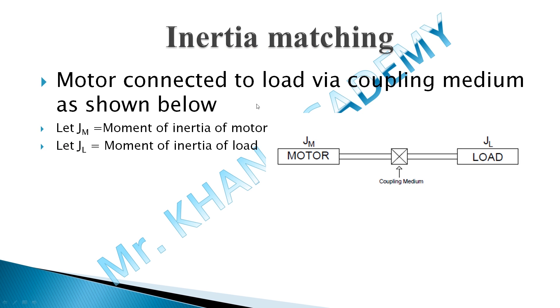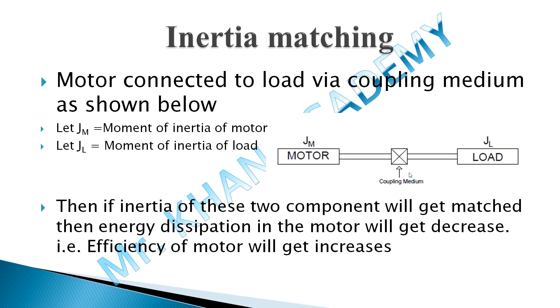Let's start inertia matching. Assume a motor is connected to a load via a coupling medium. On the motor side, the moment of inertia is Jm; on the load side, it is Jl. When Jm and Jl are matched, energy dissipation in the motor decreases, heat dissipation decreases, and ultimately the efficiency of the motor increases. Two factors influence heat dissipation: coupling ratio and velocity profile. Velocity profile was discussed in detail in 2.3; in this video we consider the coupling ratio with inertia matching.